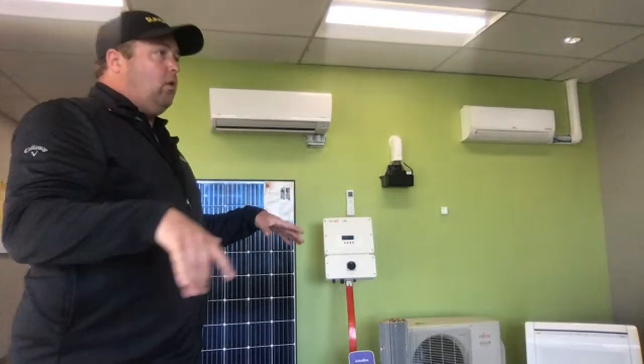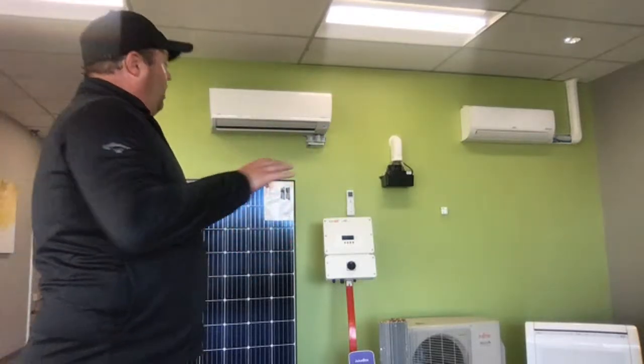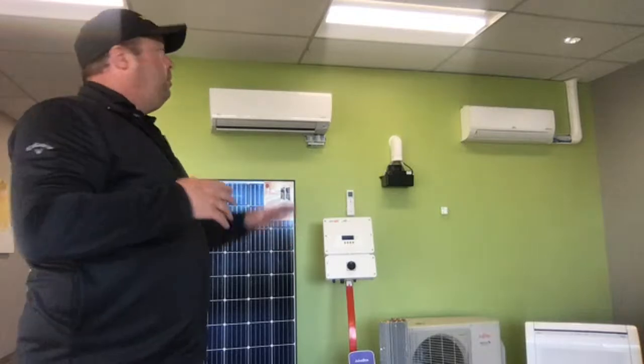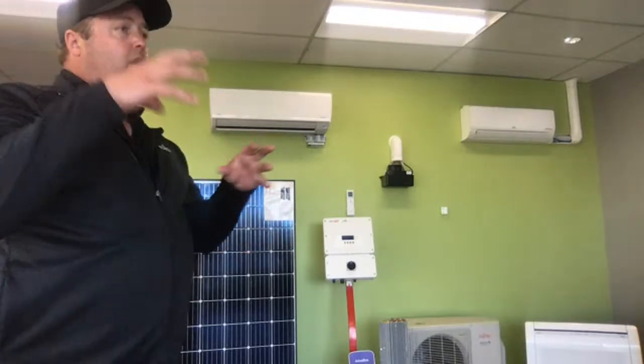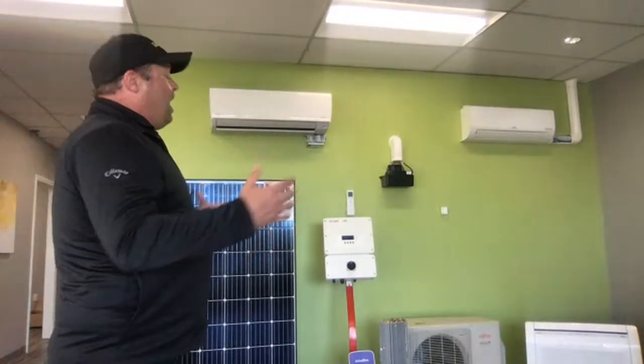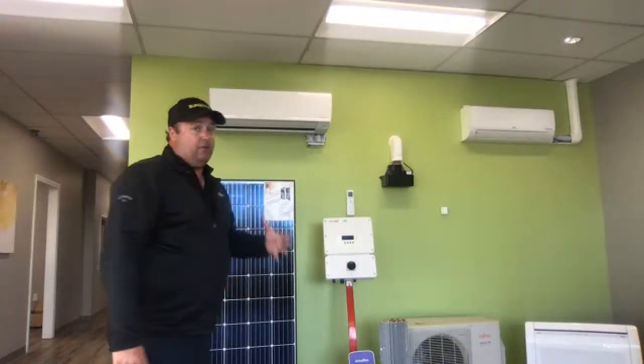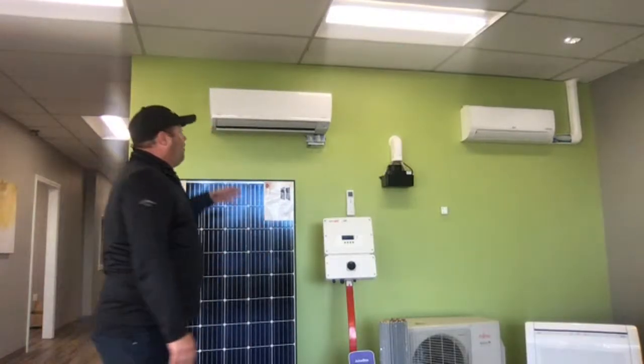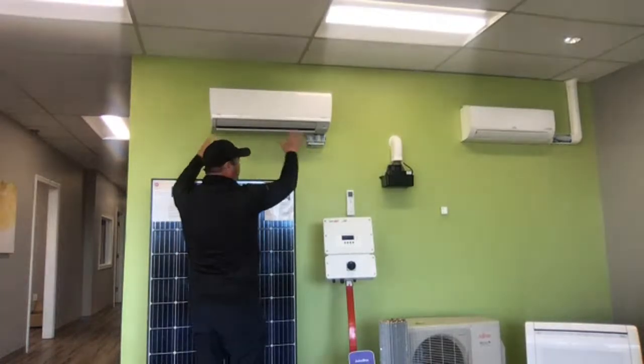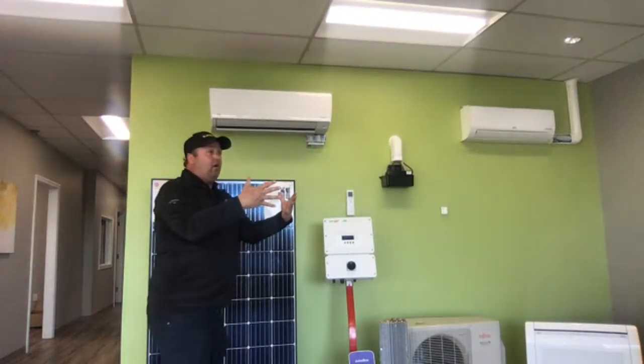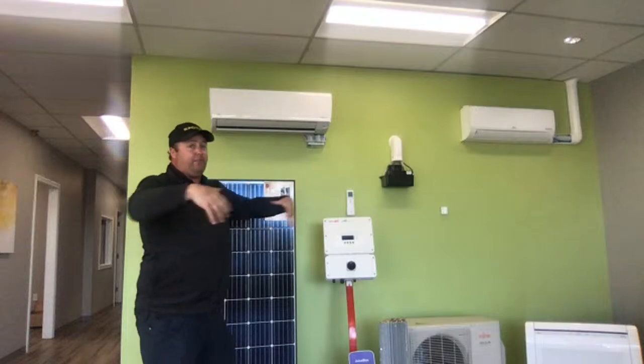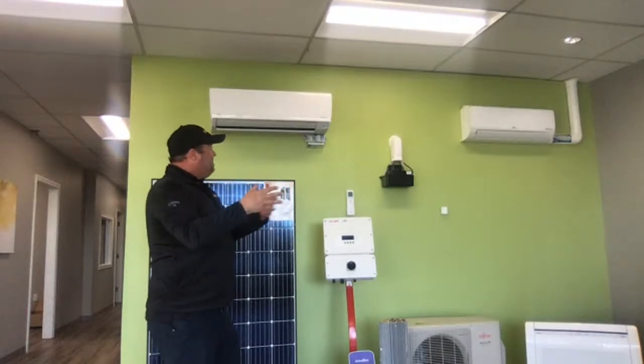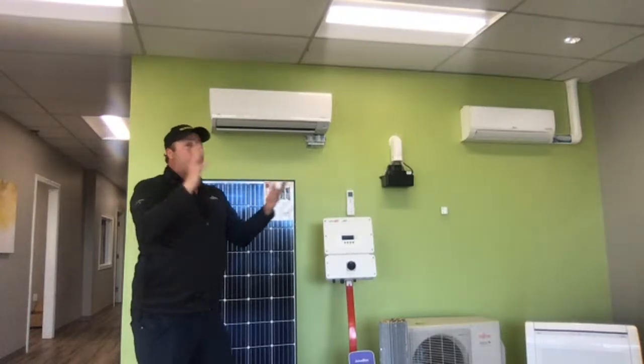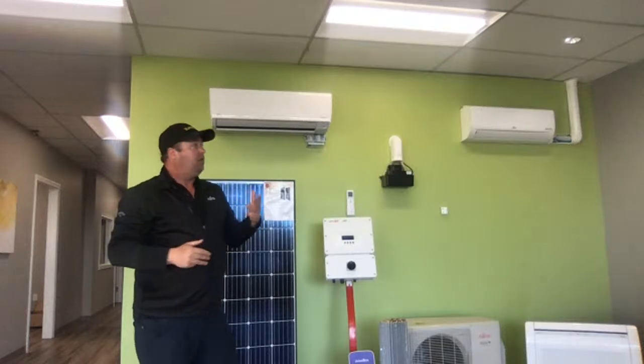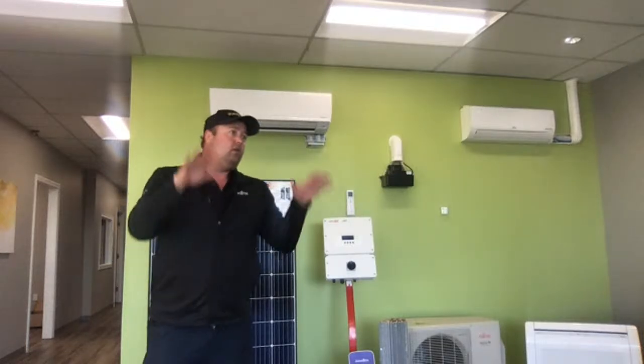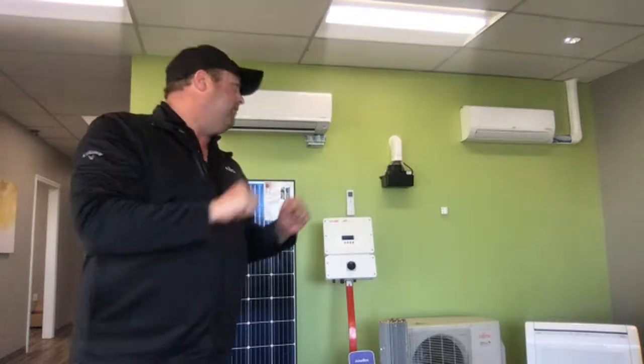They don't like doorways. You can strategically place them sometimes, but putting one in a bedroom or a small hallway oversizes the heat pump for the space. So when it comes on, it blows out all the heat, that heat traps in the immediate area, and the machine shuts off thinking it's done its job. This is called short cycling, so it just shuts off and on and off and on.